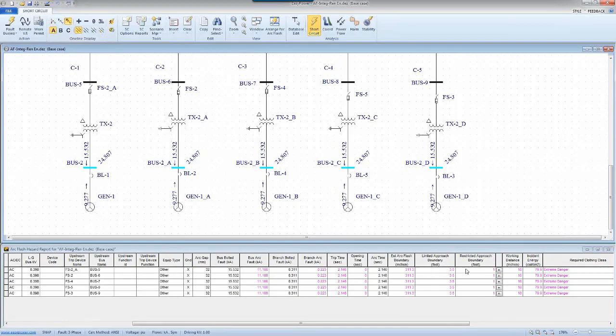Then I put it in line with my trip time, which is equal to 2. It's obviously larger than 30 cycle. It's something like 2 seconds, closer to 120 cycle. So that's why you would see this current here, which is a 30 cycle value. If this trip time was, let's say, one cycle, or 0.9 cycle, you would definitely have seen the half cycle value here, because this is an integrated method.